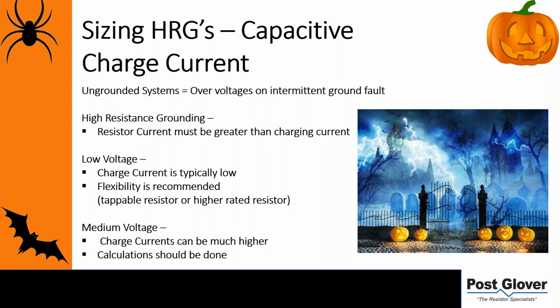In an ungrounded system, overvoltages are potential on intermittent ground faults. In fact, you have to consider 8 times your rated voltage. That is also a problem with high resistance ground systems, assuming you don't size it correctly. So obviously a design consideration would be you have to have the resistor current be greater than the system charging current, or the current associated with the system's capacitance.